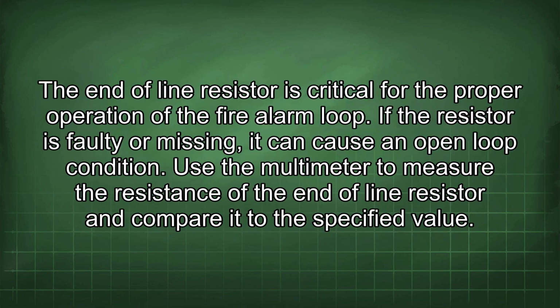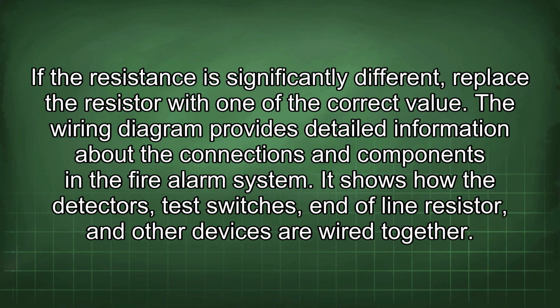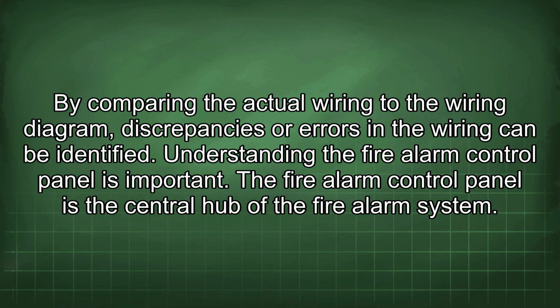The end-of-line resistor is critical for the proper operation of the fire alarm loop. If the resistor is faulty or missing, it can cause an open loop condition. Use the multimeter to measure the resistance of the end-of-line resistor and compare it to the specified value. If the resistance is significantly different, replace the resistor with one of the correct value. The wiring diagram provides detailed information about the connections and components in the fire alarm system. It shows how the detectors, test switches, end-of-line resistor, and other devices are wired together. By comparing the actual wiring to the wiring diagram, discrepancies or errors in the wiring can be identified.